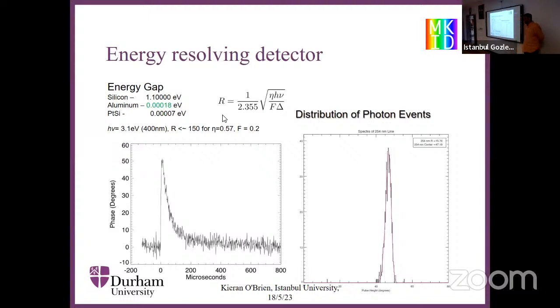In the very beginning, we have been asking initially for them to register. At that time, I remember it was quite expensive for us because it was a research lab, this instrument is not fabricated. So, is there any development regarding that direction? I mean, a cost estimate for such instruments, for instance, rough order of magnitude? Yeah, rough order of magnitude for a 20,000 pixel instrument is somewhere between 700,000 and €1 million. For the whole thing.